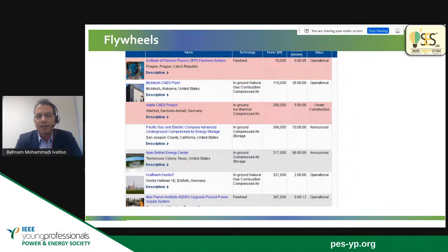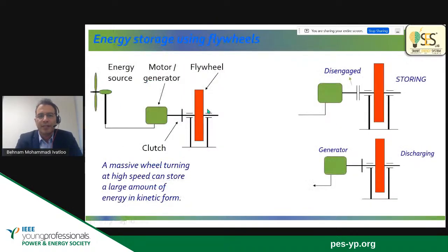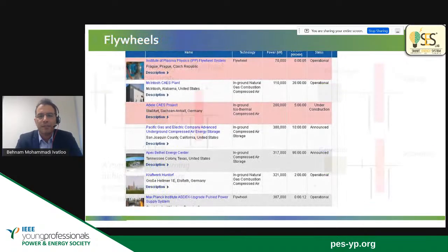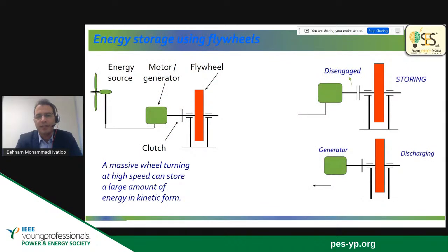Then they are using a flywheel. The motor size here, for example in the Max Planck Institute, is about 15 megawatts. This flywheel is charged by the motor to rotate, for example over 10 to 15 minutes, and after a while, when it reaches nominal speed, you can use the flywheel to discharge it at higher power.